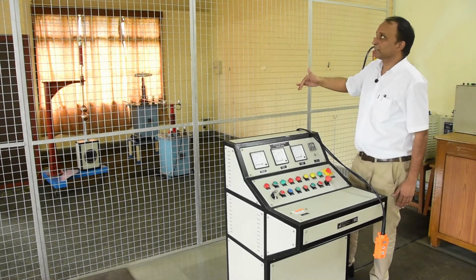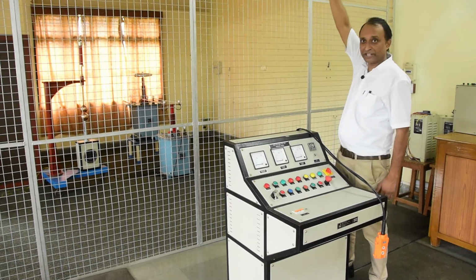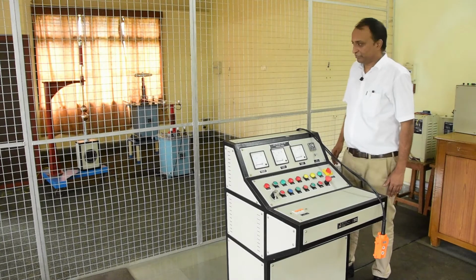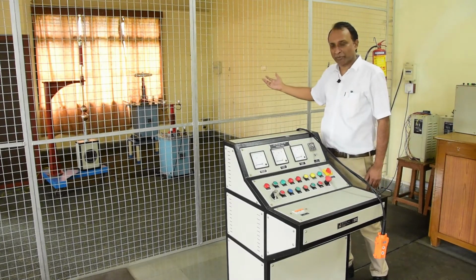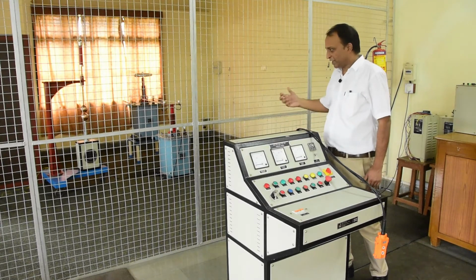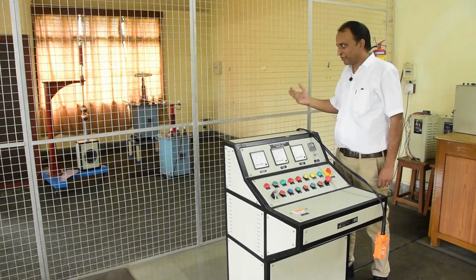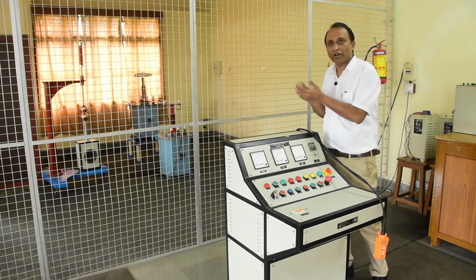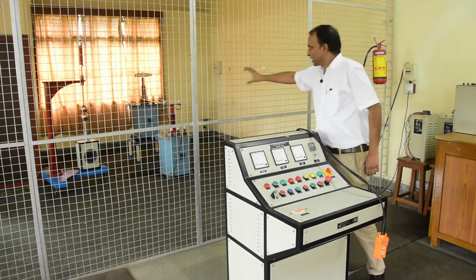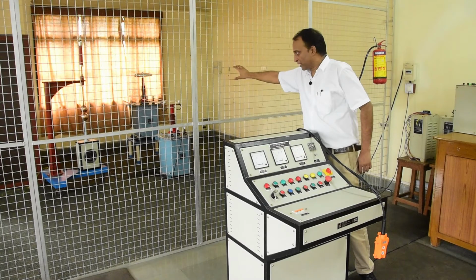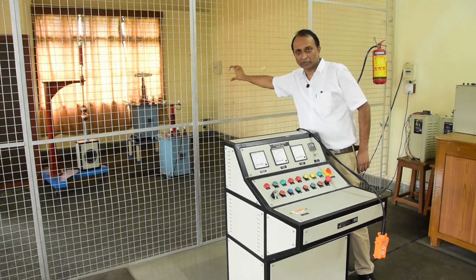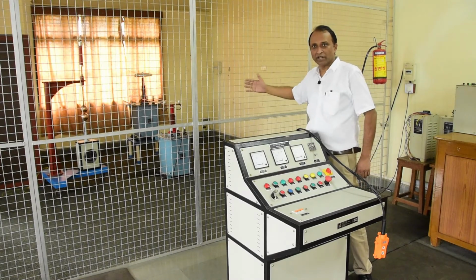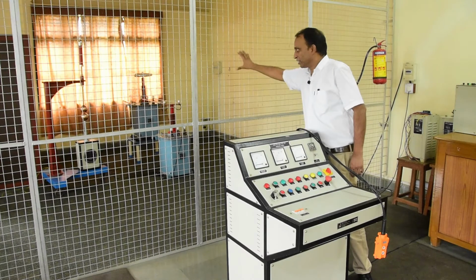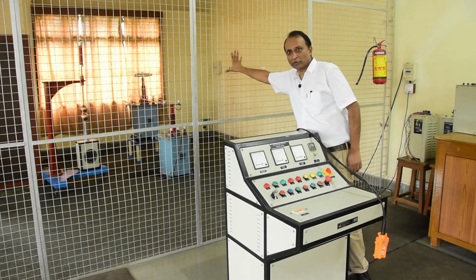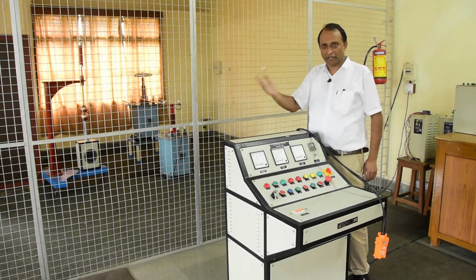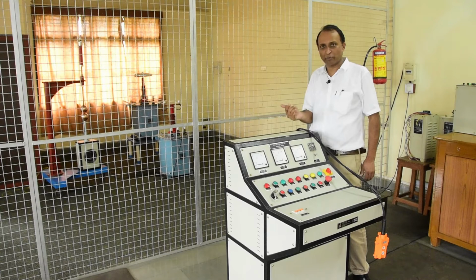This assembly is a complete enclosure right up to the ceiling of this room, because whenever we are working with high voltage experiments and applying high voltages, a very strong electric field is present, and this field has the capability to ionize nearby objects. That's why this cage is a safety feature. It is solidly grounded, so that whatever electric fields are emerging from the high voltage terminal while working on this experiment will get discharged through this cage, and the personnel working outside and other equipment present will not be affected.